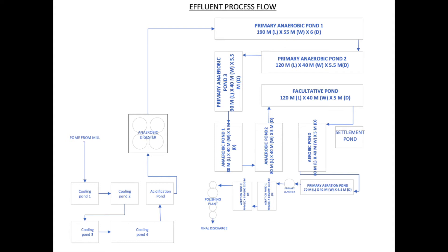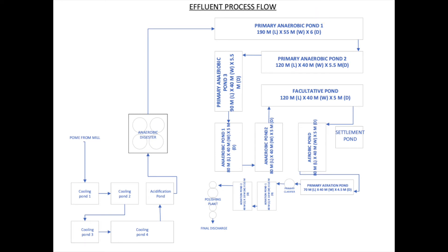When the inlet and outlet of each pond are not at the furthest distance, there will be some stasis of POME in some areas, leading to a reduction in hydraulic retention time. As highlighted, the outlet for the primary anaerobic pond is not optimally placed, and hence there may be some stasis of POME in the upper right-hand corner. On our recommendation, the sumpit outlet for the primary anaerobic pond to the secondary anaerobic pond has since been relocated.